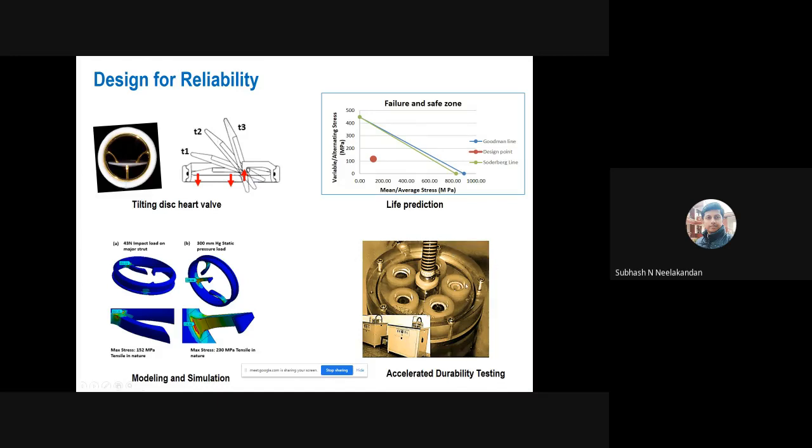And finally, since it is going inside the human body, a mere prediction or mere hand calculations will not generate confidence, and it cannot be demonstrated whether it is working properly or not. If a device has to work 50 years inside the human body, in fact, really, it should be tested for 50 years. Let us assume you are developing a device in 2020. The safe service life should be 50 years. If you start the test in 2020, it will be completed by 2070. By that time the requirement might be different, or a new device or technology will be coming. So we cannot compromise on the testing, but we need to meet the timeline also.